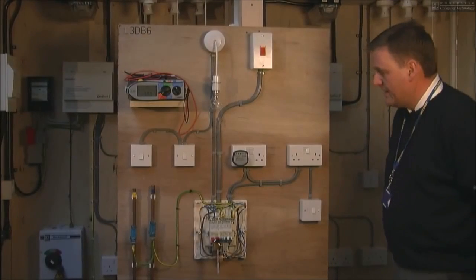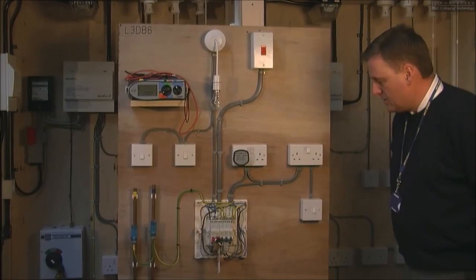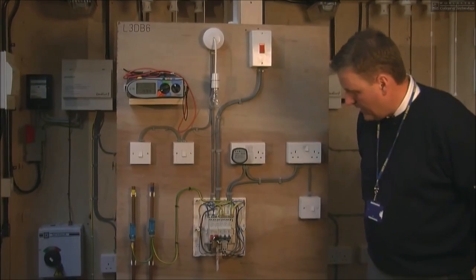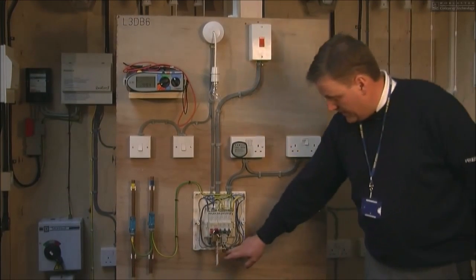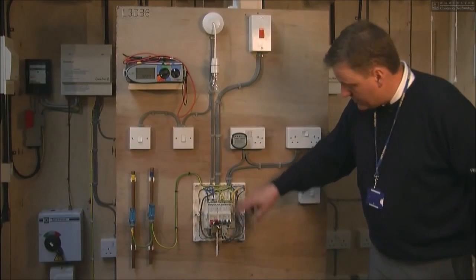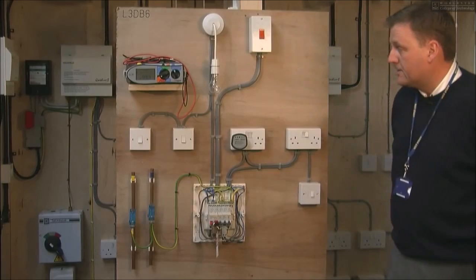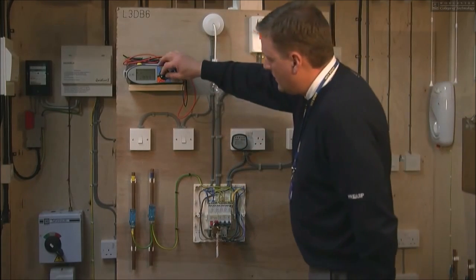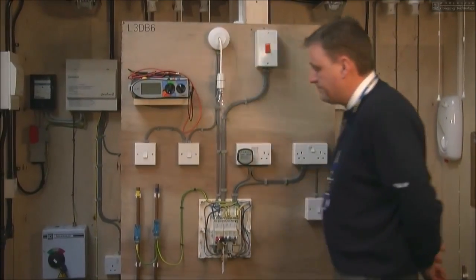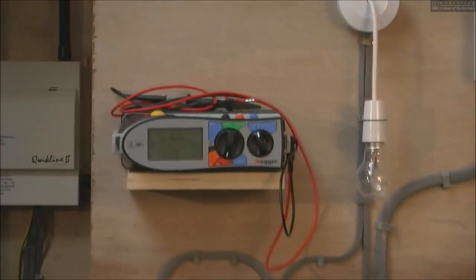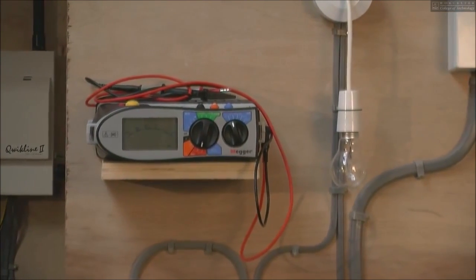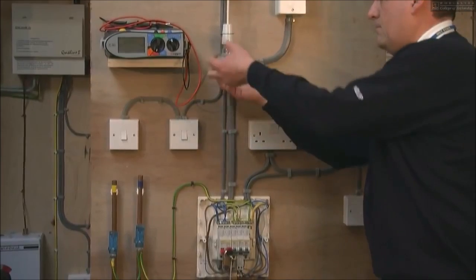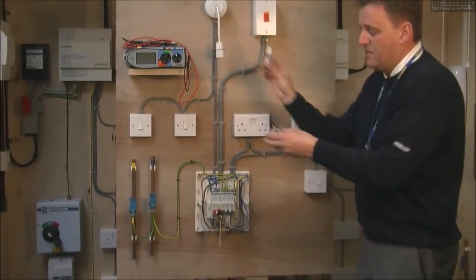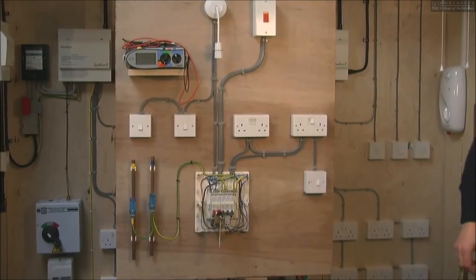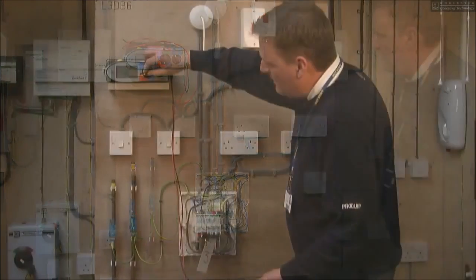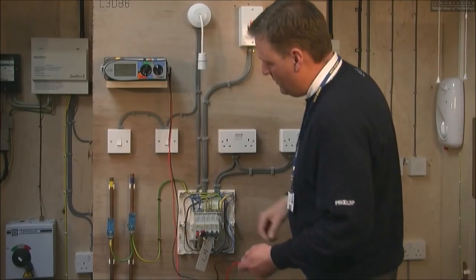Next test I'm going to perform is the insulation resistance test. This is to show that none of the circuits are actually interconnected. In other words, the line conductor isn't touching the neutral, isn't touching the CPC, and the CPC isn't touching the line conductor. So we go to the tester and set it at 500 volts. We're actually going to pass 500 volts to the circuit, so we do need to be careful of anything plugged in, so we need to remove certain items such as this plug-in tester and this lamp, because they will give us readings, as they are resistors in themselves.